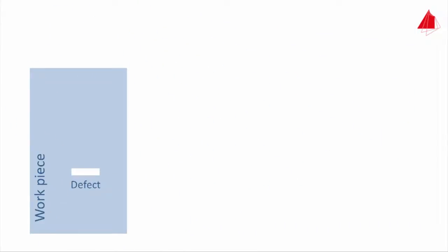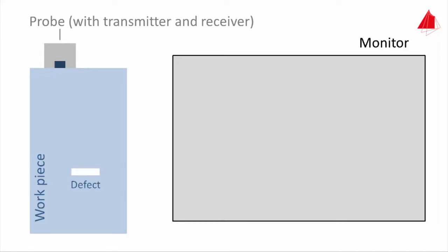In pulse echo mode, a transducer installed in a probe performs both the sending and receiving of the ultrasonic pulse. On a computer monitor, the intensity is plotted upwards on the y-axis and the time towards the right on the x-axis.